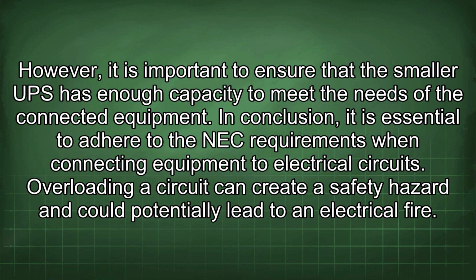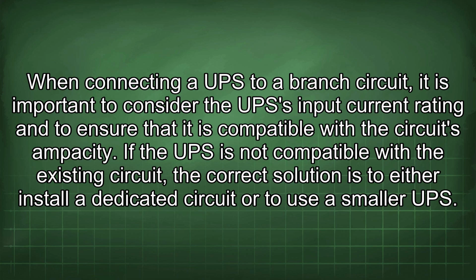Overloading a circuit can create a safety hazard and could potentially lead to an electrical fire. When connecting a UPS to a branch circuit, it is important to consider the UPS input current rating and to ensure that it is compatible with the circuit's ampacity. If the UPS is not compatible with the existing circuit, the correct solution is to either install a dedicated circuit or to use a smaller UPS.